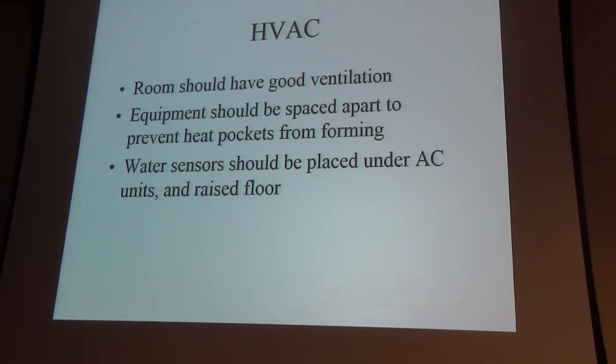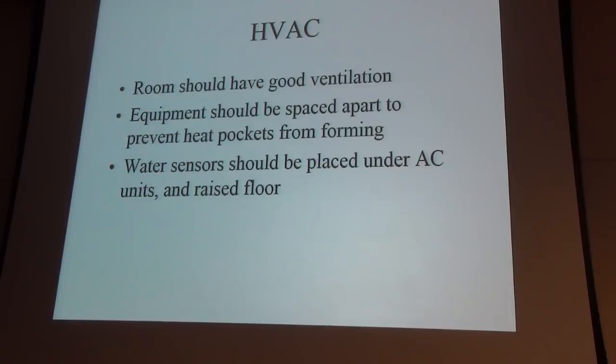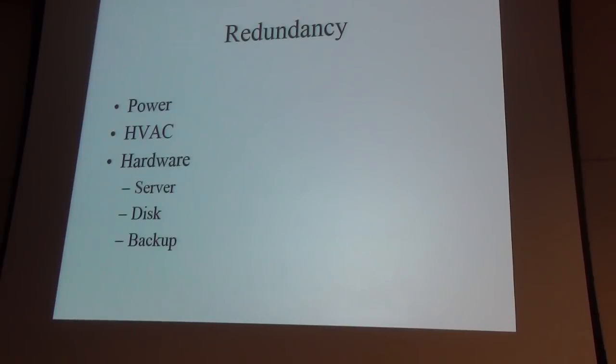Ventilation is always important. When they forced me into that basement, it was never built for a data center. We had spots where you'd feel warm air walking between racks — very uneven airflow. Part of it was because on the raised floor, cables underneath were blocking the cool air coming through perforated tiles. Some places were getting cold air, some were not. When the air came up it was swirling and completely uneven — naturally bad for equipment. To fix that they put in dozens and dozens of sensors.